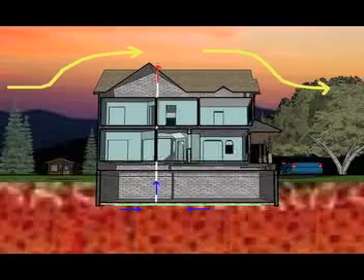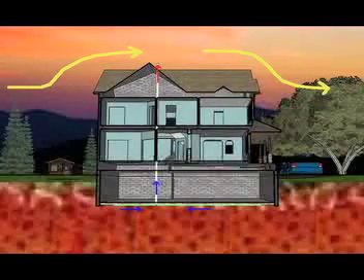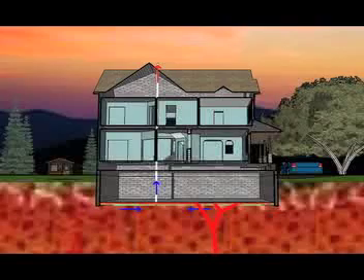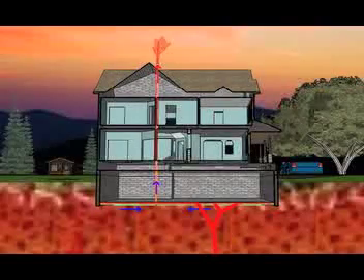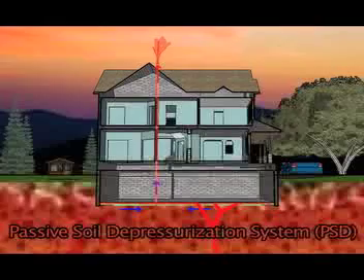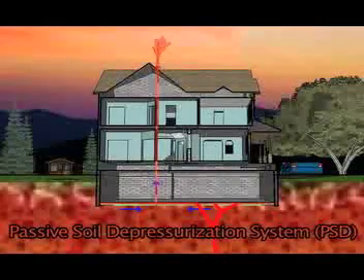With these forces acting on the channel created, gases can be drawn up from below the house, and the soil becomes depressurized. Radon and other soil gases now have a way of working their way up to the surface without going through the living space of the home. A system like this is known as a passive soil depressurization system, or PSD.